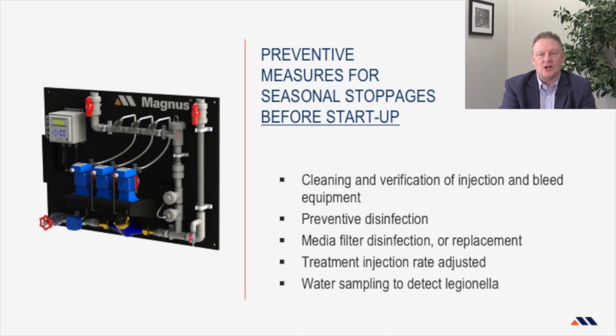Cooling tower startups also require a fair share of preventative measures. For example, if a mechanical clean was not completed at the stoppage, it must be done before the startup. The injection system and controller should be verified, cleaned, and calibrated. If you have a filtration system, it should also be inspected. The filter media must be analyzed, disinfected, or even replaced, as it could become a major source of bacterial proliferation.